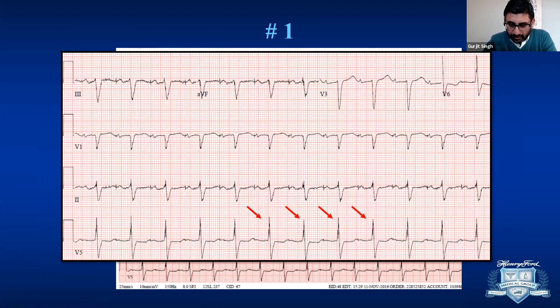So you see an atrial pacing spike, and definitely there's atrial capture, and then there's a QRS. Now this QRS does not look like a paced QRS. Now you can argue maybe BiV QRS, but look carefully at the peak of this QRS. The next slide will show. At the peak of the QRS, you will see there's a pacing spike actually. So there is something going on with the ventricular pacing spike. Clearly this pacing spike is happening after the QRS has begun, which means it cannot be a paced QRS complex. You should not see a pacing spike if there is an underlying rhythm. So this goes down to the fact that this pacemaker's ventricular lead is undersensing the ventricular signal, correct?